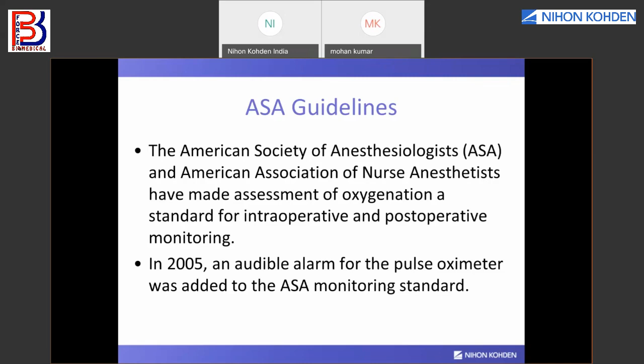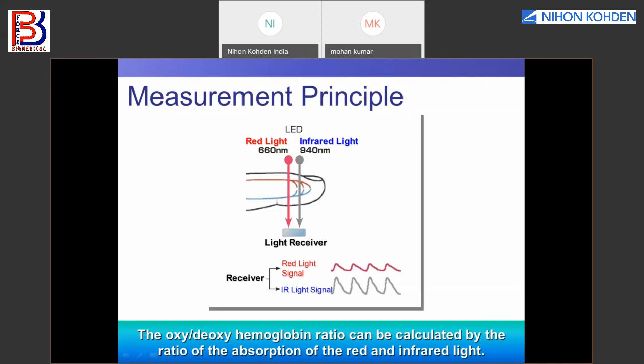So coming back to the measurement principle, if you look at the SpO2 probe, there is a red light and an infrared light emitted from the probe. There are two LEDs in the SpO2 probe: one is a red light emitter and the other is an infrared light emitter. The red LED emits light at 660 nanometers, and the infrared LED emits light at 940 nanometers. The light passes through the fingernail, and at the receiving end the light is absorbed. Based on the absorption of the red and infrared light, the SpO2 is calculated and shown on the display.